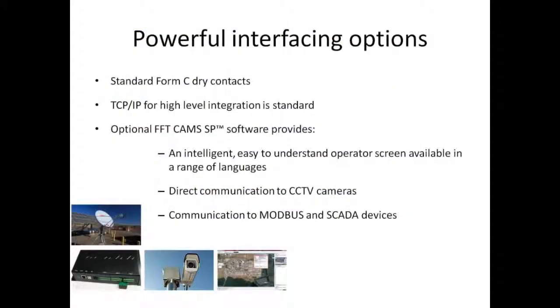Lastly is interfacing the alarm outputs from the SecurePoint unit. This can be through the standard Form C dry contacts or TCP/IP for high-level integration. Both are standard on the units. Also available is the optional FFT CAMS software, which provides an intelligent, easy to understand operator screen available in a range of languages. CAMS also provides direct communication to CCTV cameras, Modbus and SCADA devices.